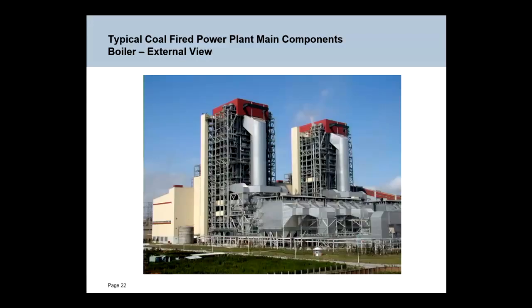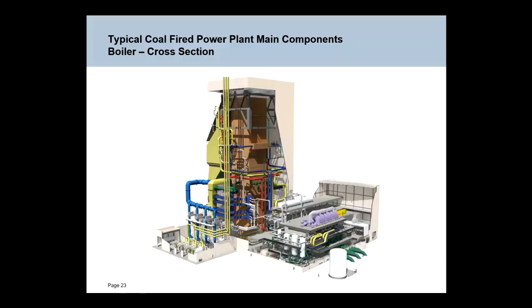Okay, and then photographs. So this is a 2-unit power station. Here we're looking at the back of the boilers. This is the gas cleaning equipment here. The turbine house is at the front here, you can see. So there would be 2 turbines at the front of this thing. These are 2 units. And similarly here, this is a cross-section of a single unit where you can see the boiler cross-section, turbine here up on its foundation with the condenser hanging below. And for scale, you can see this is a human being walking across the concrete here. So again, it's a very large piece of equipment.